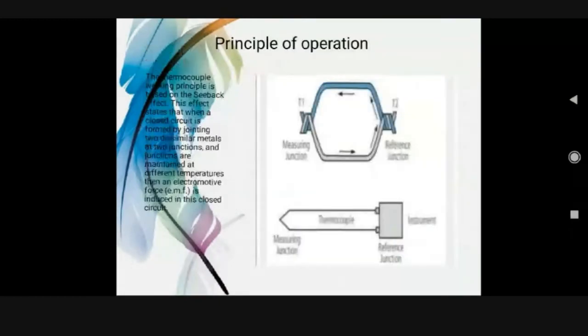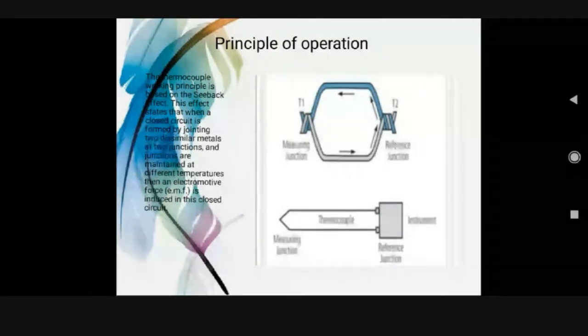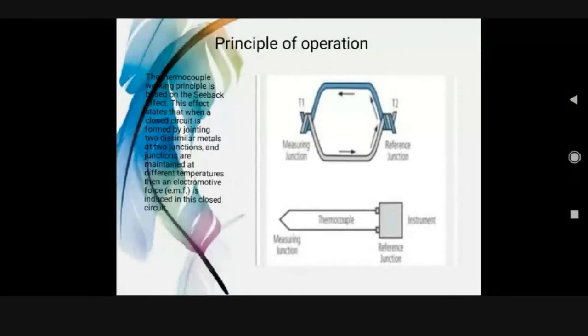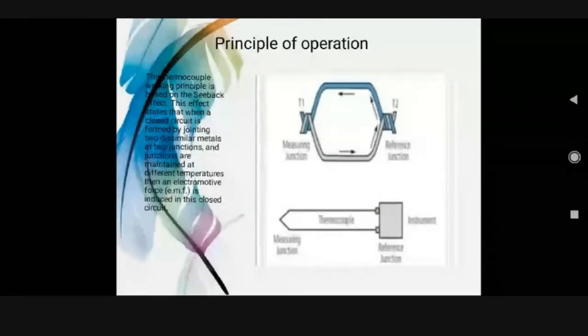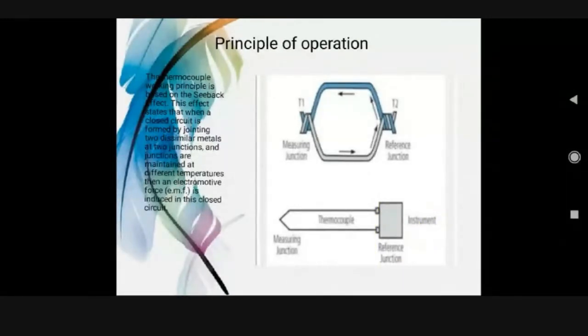Principle of operation. Thermocouple working principle is based on the Seebeck effect. The Seebeck effect states that when a closed circuit is formed by joining two dissimilar metals at two junctions and the junctions are maintained at different temperatures, then an electromotive force, EMF, is induced in this closed circuit. We can see there are two junctions. This is the measuring junction and this is the reference junction. In the measuring junction, these are the two dissimilar metals joined at the end, and when this measuring junction is heated or cooled, we can see the temperature at the reference junction, and we have to connect an instrument like a multimeter to it. Then the multimeter shows the temperature.